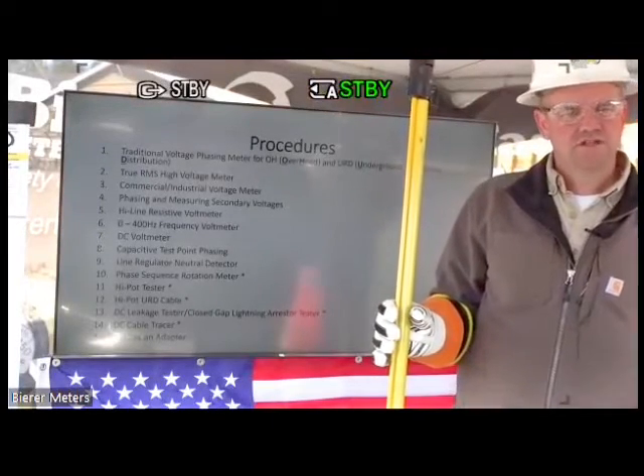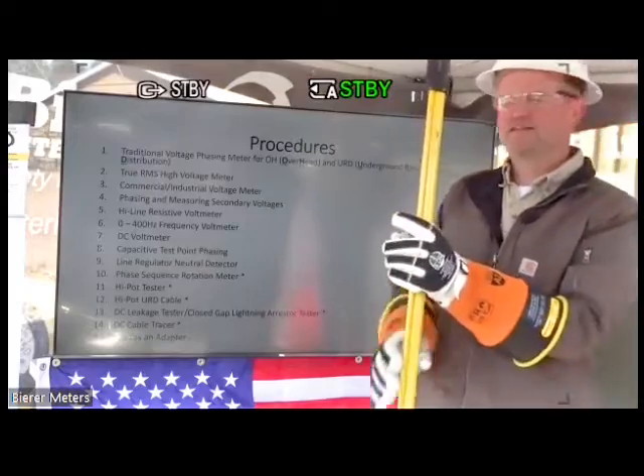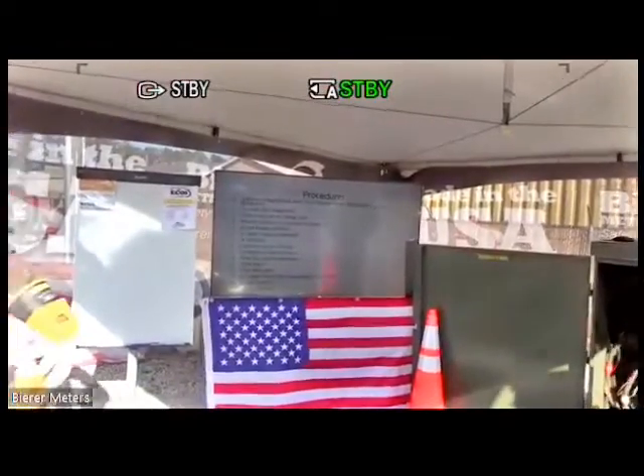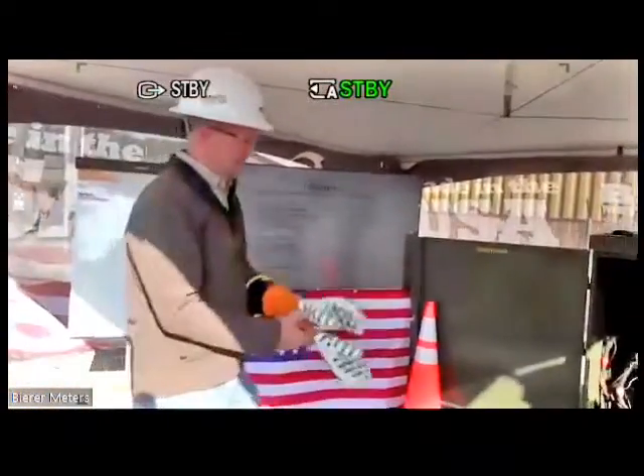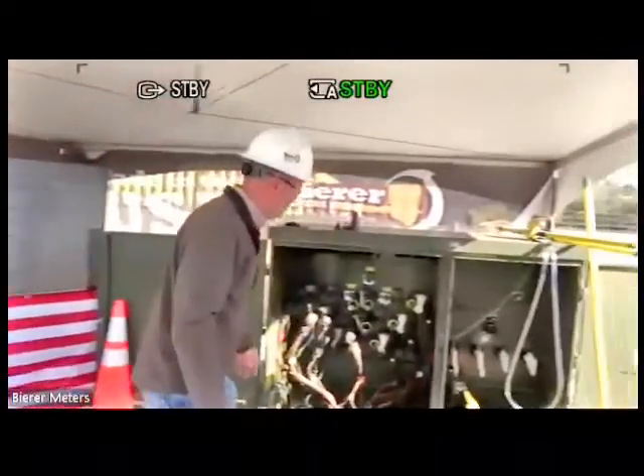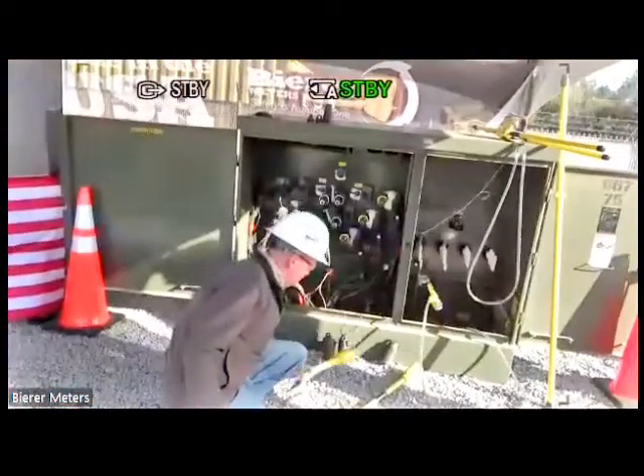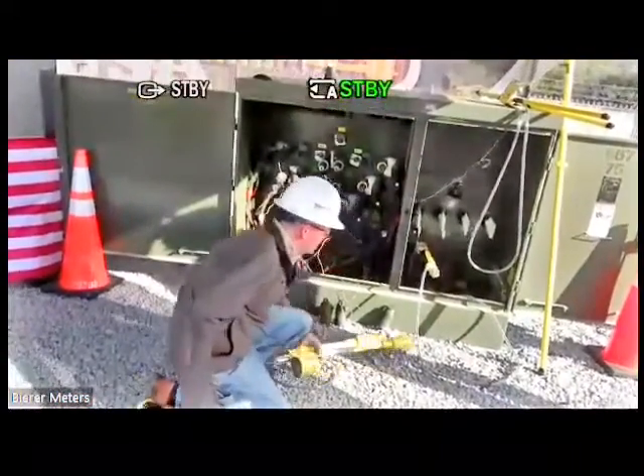With other manufacturers, I can use a PD25 to actually test the high pot. So if I want to use the PD25 as a phase sequence rotation meter, and again, I can do this in secondary applications or primary, it doesn't matter. And the first one I'm going to do is secondary.